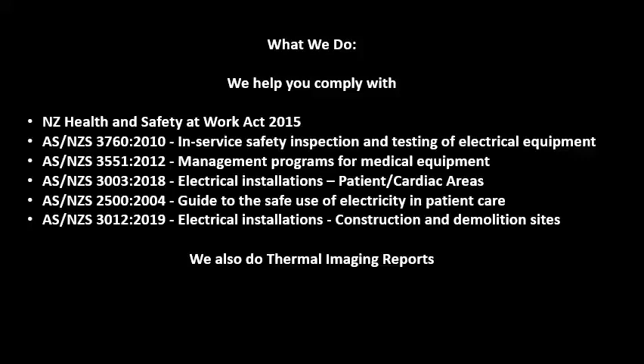3003 is again a biomedical standard, and it talks about the patient and cardiac protected area, or body protected areas - places like hospitals, doctors' waiting areas, and doctors' rooms, where they're checking a patient using biomedical equipment under 3551. The predominant requirement under 3003 is that the room or outlet is protected by an RCD, a residual current device.